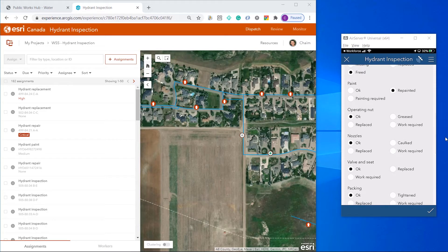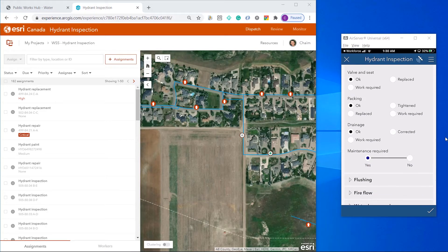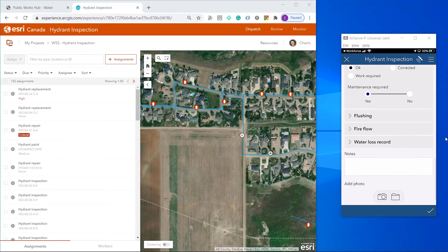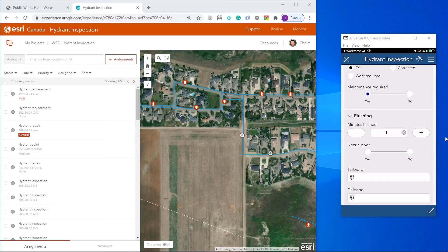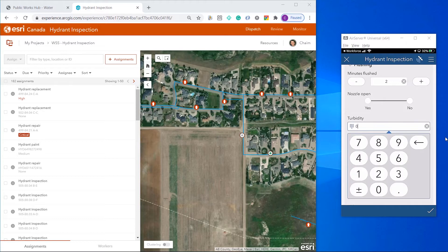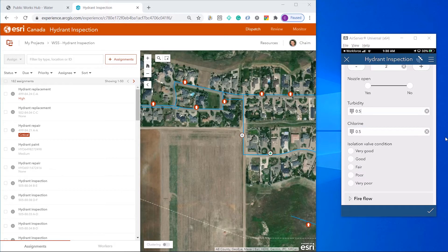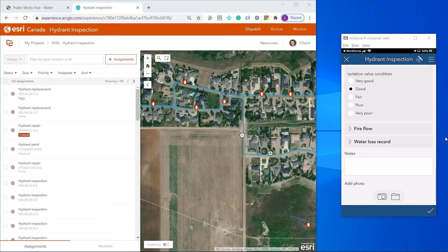Now, if I change the painting to Painting Required, this field will flag this inspection as one that requires follow-up. I flushed the hydrant for two minutes and I can capture some additional observations: Turbidity, Chlorine, and Condition of the Valve.